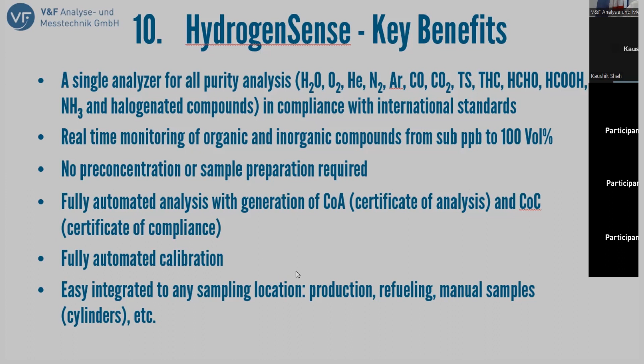I've already mentioned that we are not using pre-concentration or sample preparation. It's pretty much sample gas goes from point A to B, then comes into our sample switching module, and will then be introduced into the mass spectrometer. Something that we offer, but which will not be covered in this webinar, is a fully automated solution, which is a piece of software that we currently call Premier Guard. It has an auto scheduler, certificates, printing, calibration, gas supervision, and things like that. For example, on a production site, when you want to schedule analyses within certain time frames, this can all be done in a fully automated way. Here, during this webinar, I would rather go into the basics and show you how signals are produced, how the instrument responds, and how an analysis can be done.